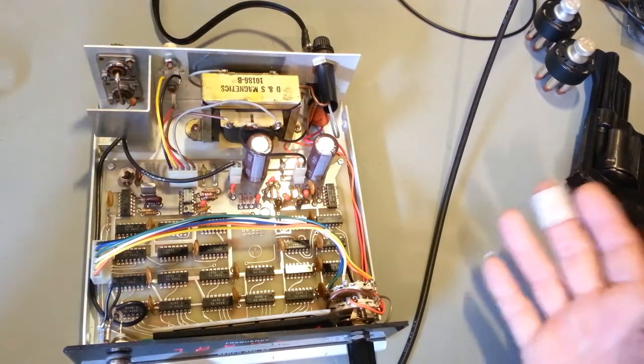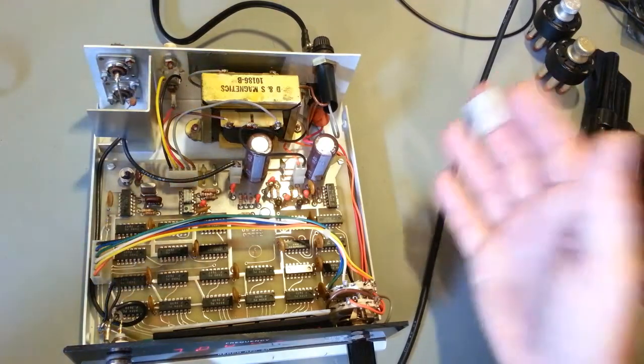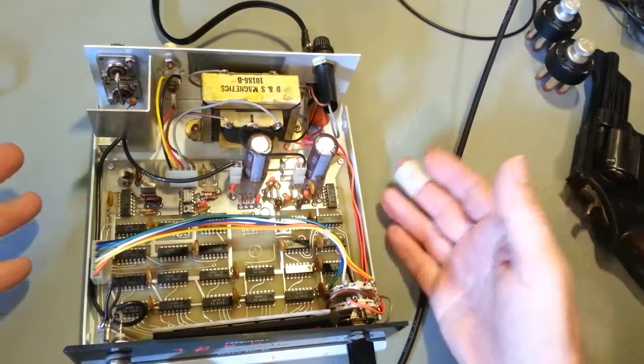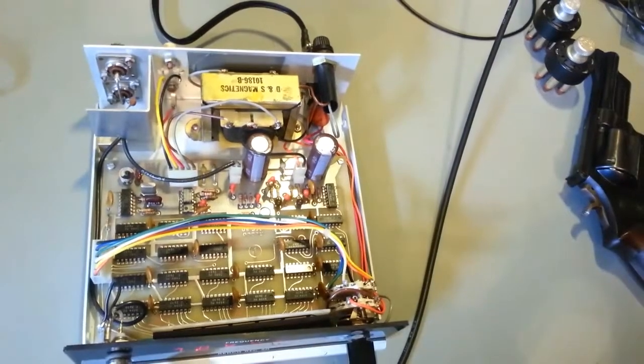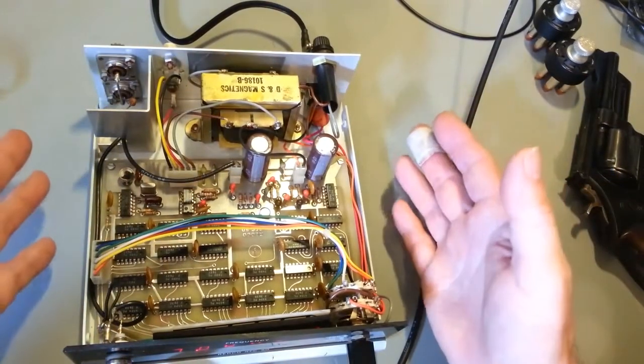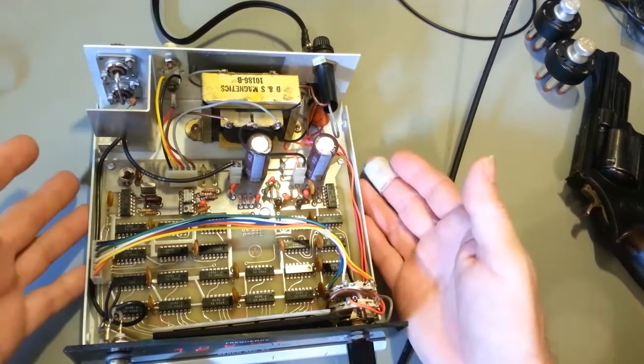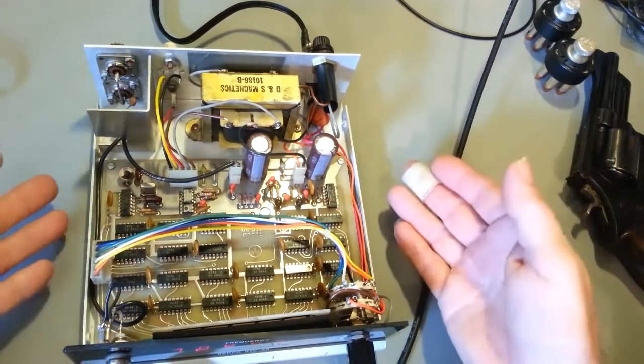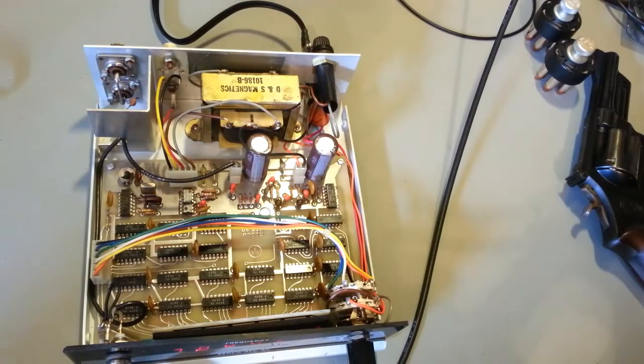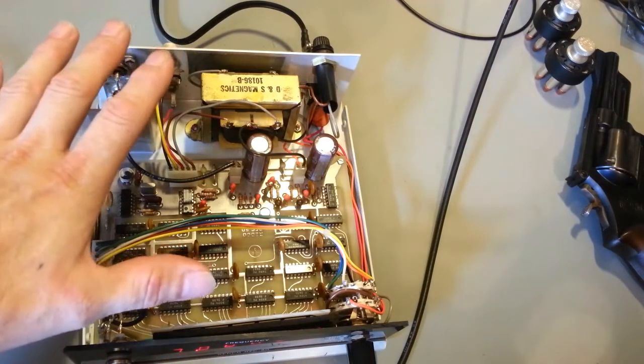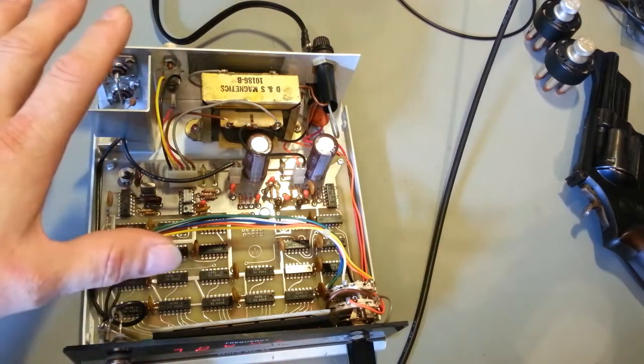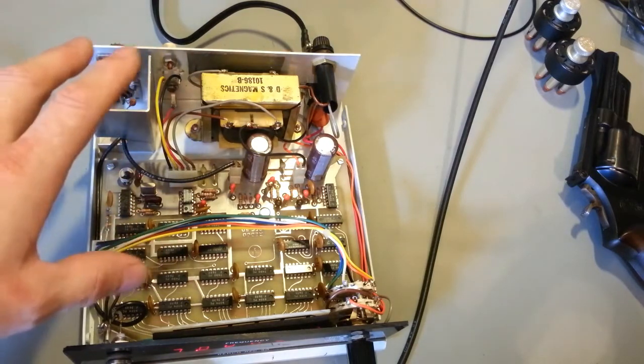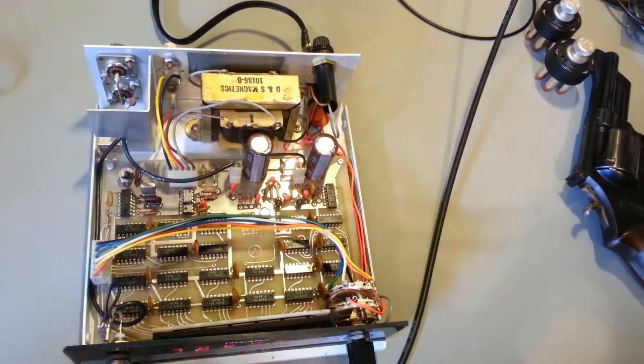So it's just a pass through here with a small sample port. They work well for what they're designed for, but like I said, it's not a lab instrument so don't expect lab quality readings off of something like this. But to try and get it as accurate as possible, when you use something like this, don't expect it to be accurate cold. You should turn it on and after 45 minutes or an hour, that's probably when it's going to be starting to get close to the point where it's going to reach its best stability because the entire unit will have had time to warm up.